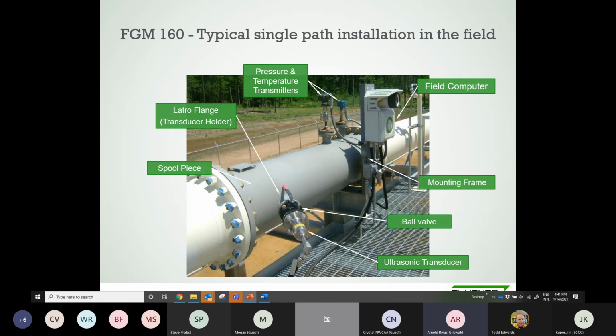The signal is generated and sent to, for example, this upstream sensor, shot through the medium to the other side and received by the other sensor, and then it comes back to the flow computer. It's also analyzed here. When the same signal that we send is verified as received in the flow computer, we take the time of flight. Then we do the same process through the opposite side, and the time differential helps us determine the velocity.